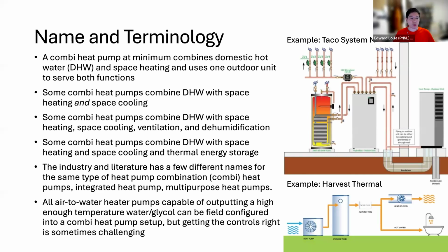When we say Combi heat pump, the industry has traditionally used that with a broad brush in terms of what it can do. What are we combining? Some Combi systems can combine domestic hot water with space heating and space cooling, while others can only do space heating and domestic hot water. Even some more systems can do domestic hot water, space heating, space cooling, ventilation, and dehumidification. And then some other systems can do the space heating, cooling, domestic hot water, and integrate thermal energy storage.